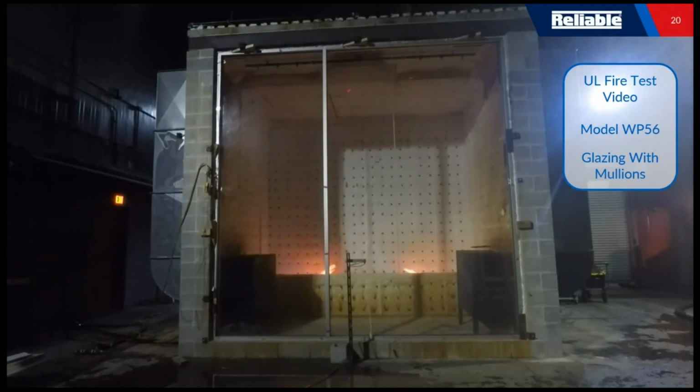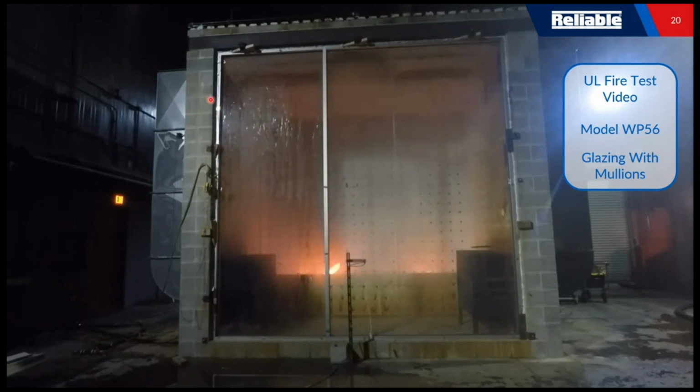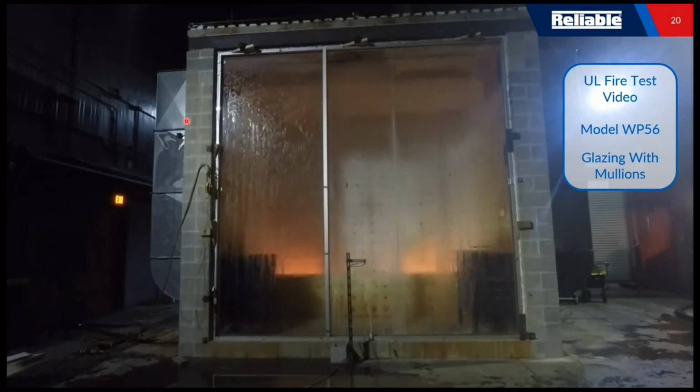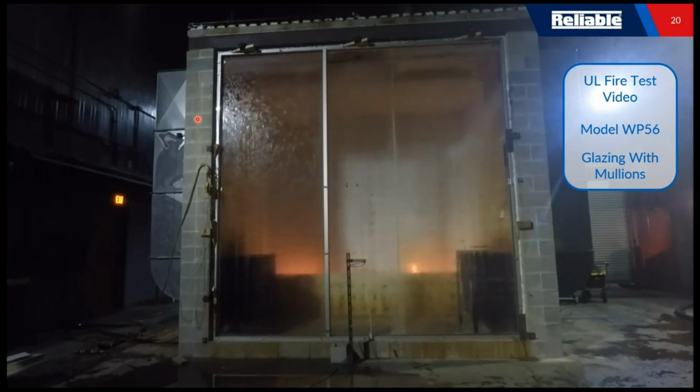We have a video here of our testing, and this is the area I want you to focus on. You can see as the sprinkler starts to discharge, there's actually some dry spots on this glazing material. And as it flows, that's going to slowly, completely fill in with water, and bring in that cascading sheet that goes over top of this, insulating that glazing material 100% from anything that's going on in that compartment.